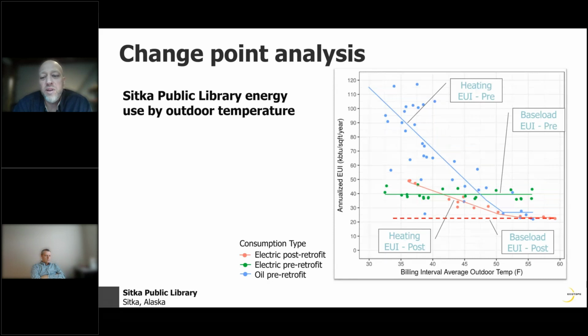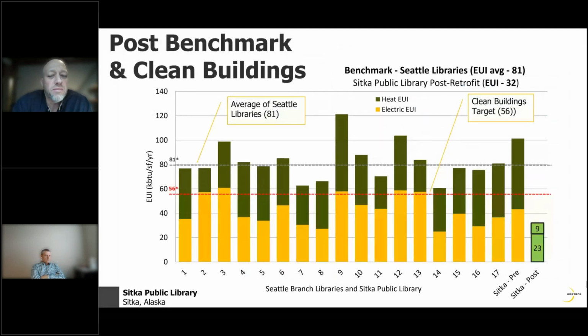You can see the base load went from 40 to 20, mostly from LEDs and upgrades to plug loads and computers. The space heat load, the temperature dependent EUI curve, is about half the slope there. That's a pretty key indicator of a high performance building - seeing a slope that shallow.